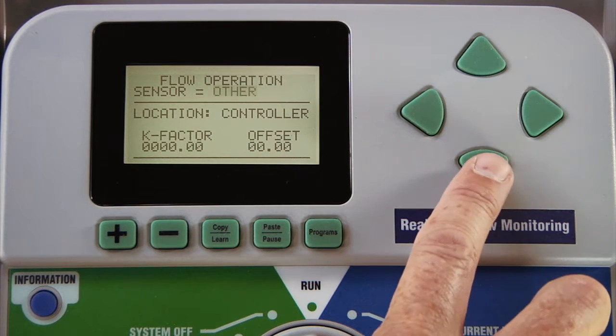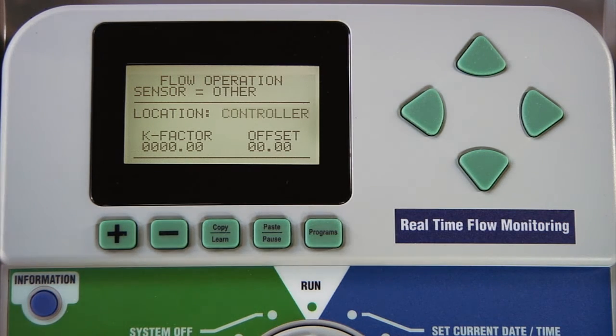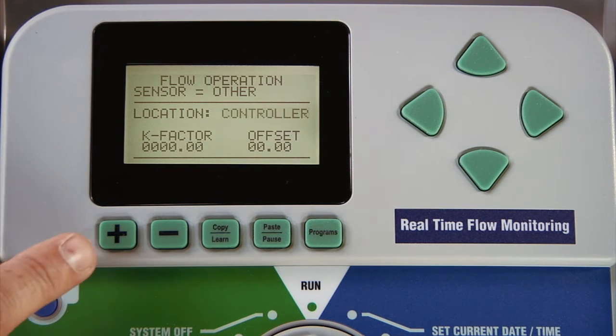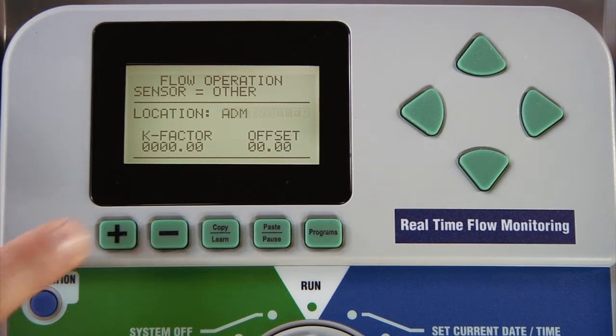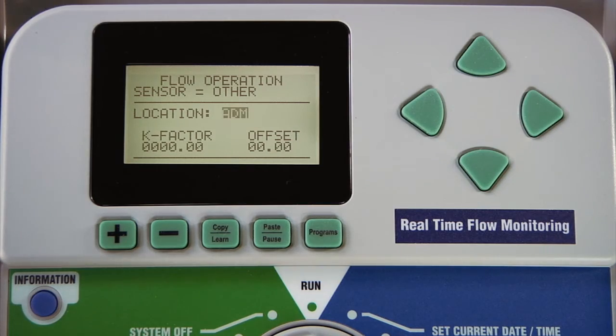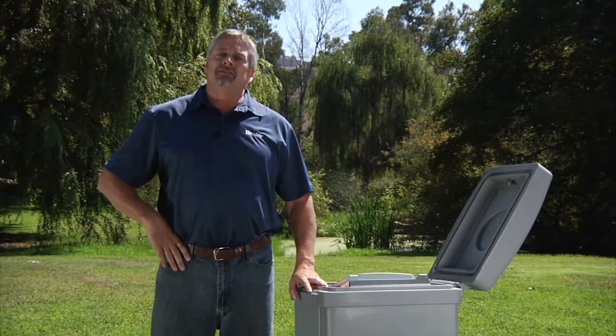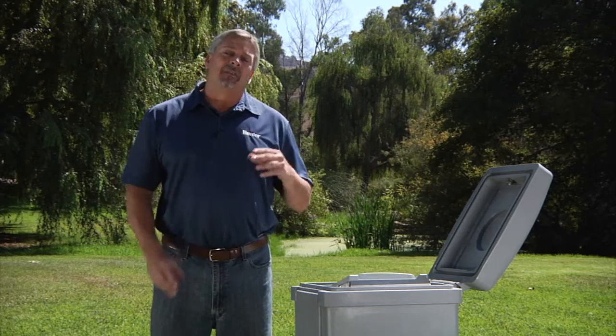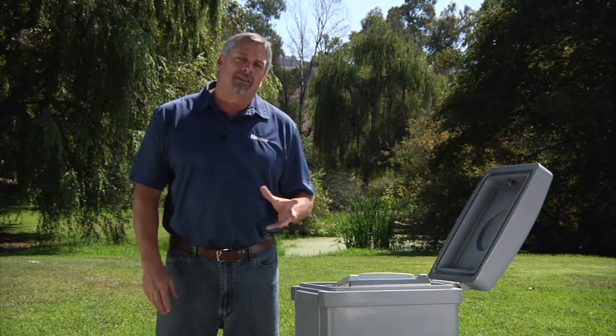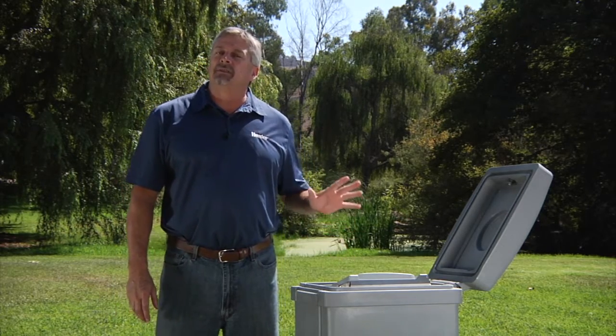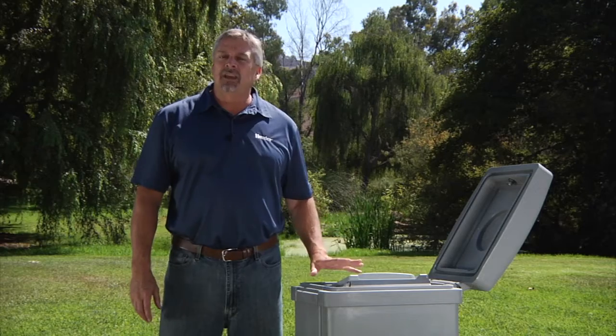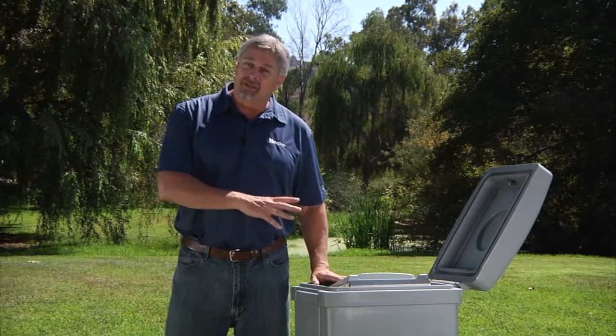The other selection, using the down arrow, brings you to the location. Here it says controller and we'll need to change that with the plus button to ADM. That tells the controller to look for the flow information on the two-wire path as opposed to being hardwired directly to the controller. So if you have the flow sensor connected to a decoder on the two-wire path, you have to make sure that the flow sensor is mapped as far as its location to ADM or decoder in the controller.